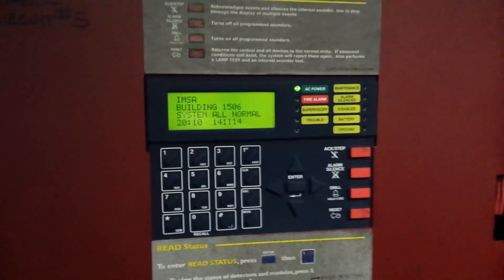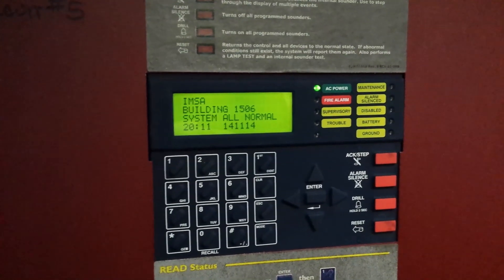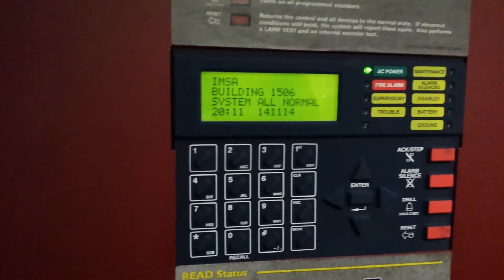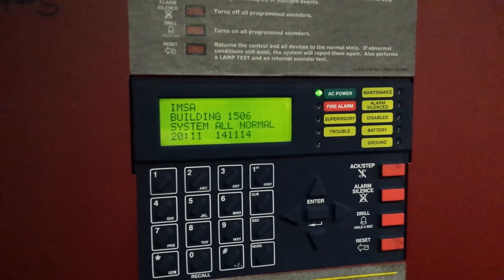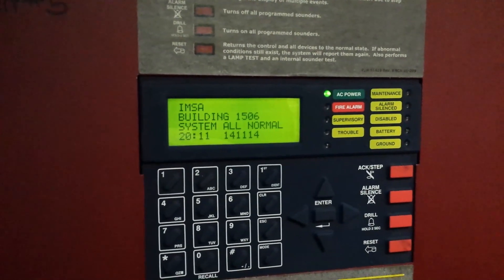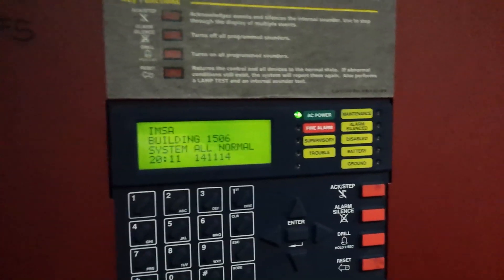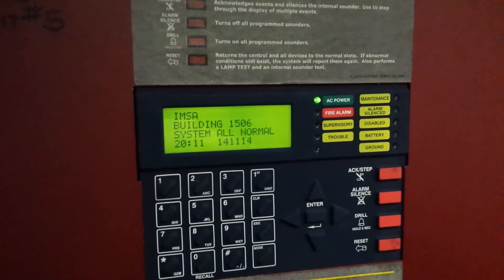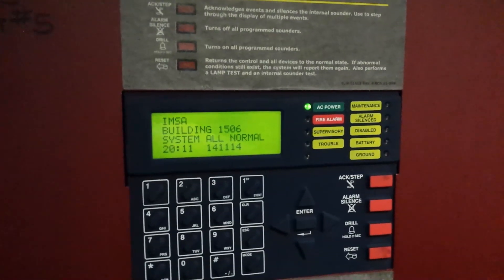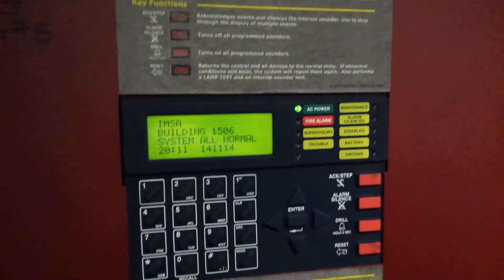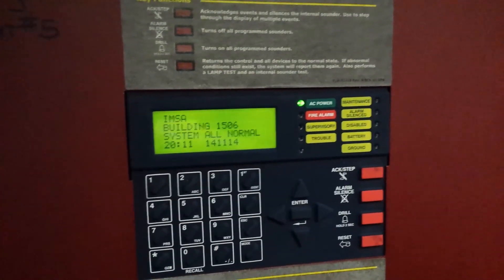This is a Fire-Lite MS-9600 panel version, I think it's 2.6. We can check the firmware when we're done here, but the customer was told that the AVs weren't activating on the second floor. I observed that the second floor, which is on loop two, the smoke detectors are not blinking, so we're going to go up and take a look at that right now.